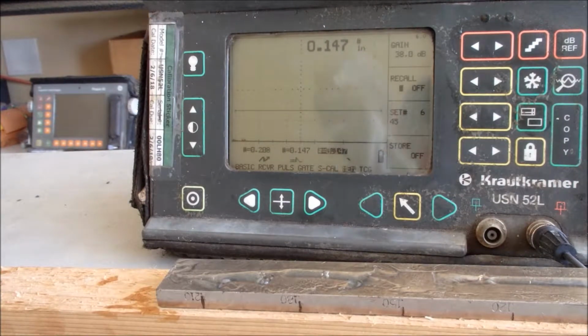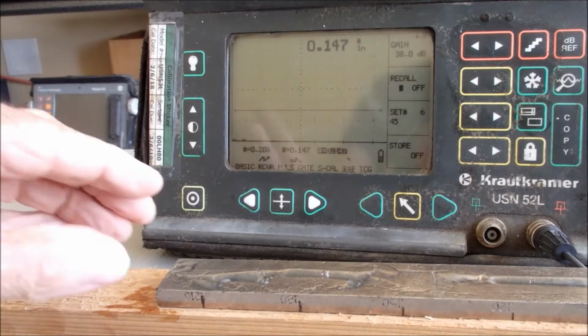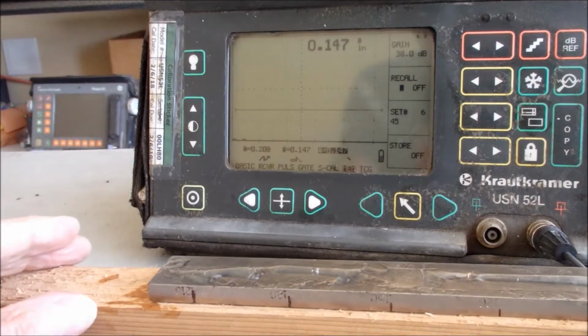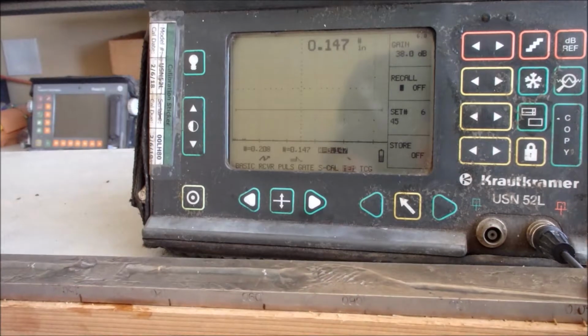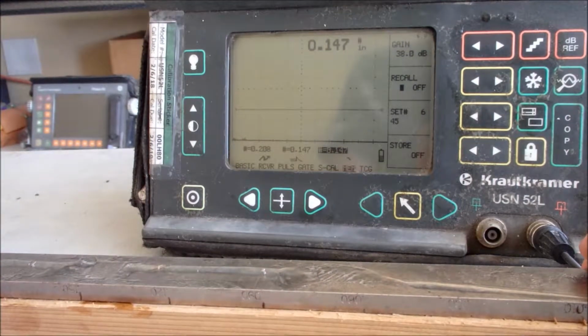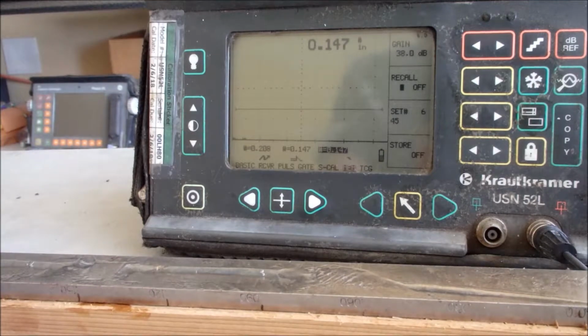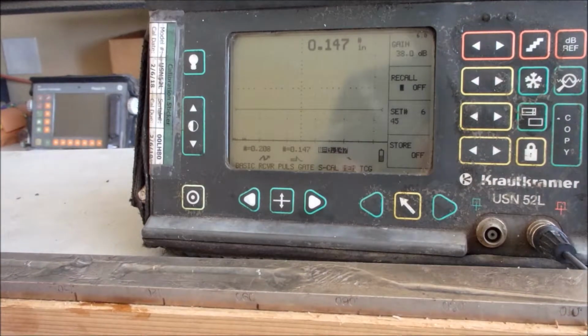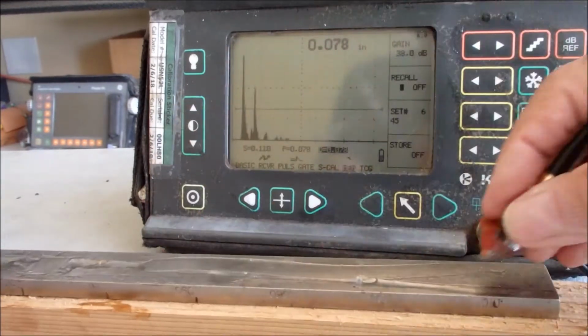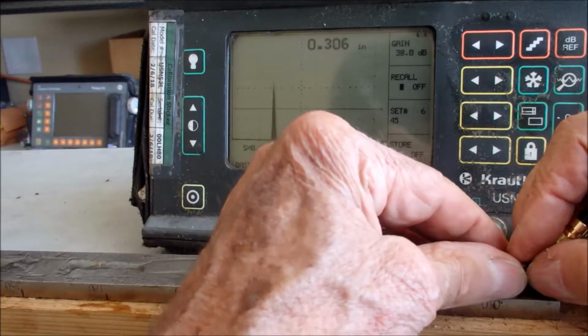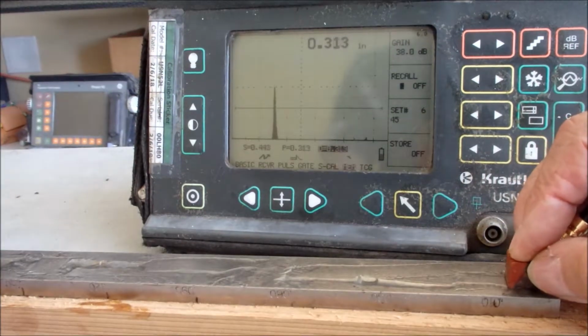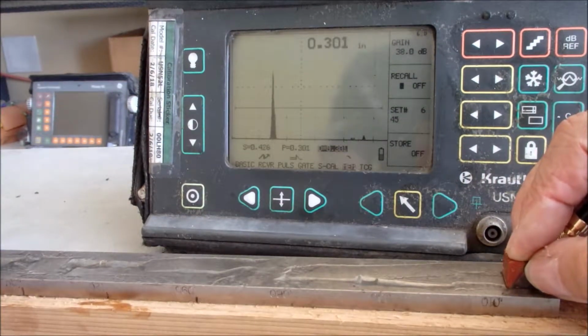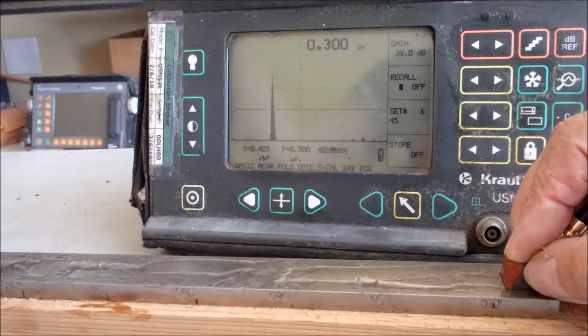All right, so we're going to try to do this with 6 dB drop amplitude sizing, and I'm going to look at each of the notches, bring it to 80%, and then move the probe to get it 6 dB less at 40%, and then we'll take our measures. So I'm going to start with the 10 thousandths notch. Here's the 10 thousandths deep ID notch. Pretty close, near to 300 deep where it's supposed to be.